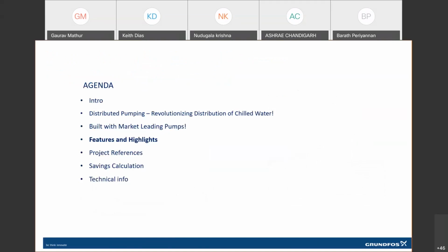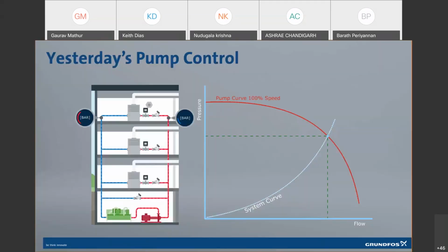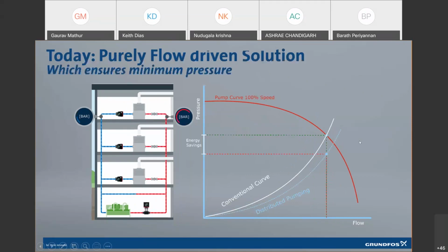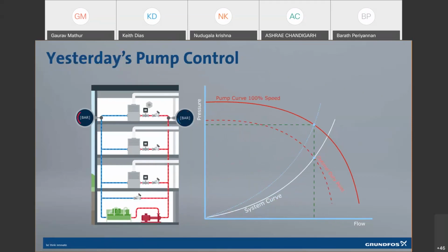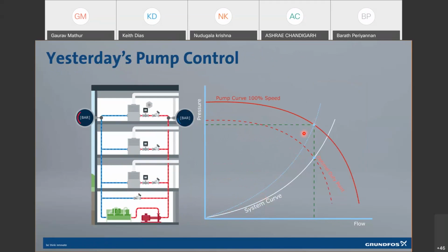We can talk about so much savings in pumps, but there has to be a logical answer as to how those savings actually happen. And that is what we see here: in a conventional system, you have something called a system curve, and the system curve is changing with the changing load requirement. This is essentially what is happening when you have a load variation in a conventional system. The valves are closing and the system curve moves towards the left. I'm sure you are all aware of what happens to the system curve when throttling happens.